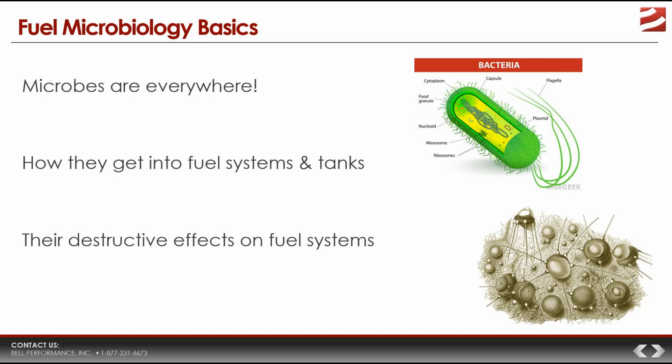Those kinds of things are what are typically characterized as non-corrosive damage. But then there's also corrosive damage, which involves metal and metal surfaces. And there are multiple serious avenues of microbially induced corrosion to metal surfaces, whether it involves the formation of, let's say, electropotential gradients and galvanic couples, which can happen when you have biofilm contamination of surfaces. You can have localized pockets of oxygen that develop, which creates kind of an osmotic situation where oxygen will want to move from areas of high concentration to areas of low concentration.